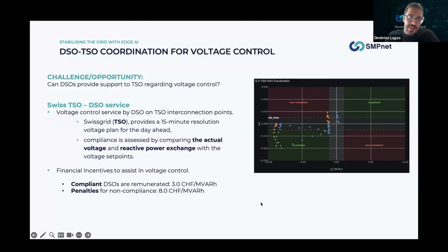And through this service, there are financial incentives for the system operator to be in the compliant regions. So they are compensated for reactive power that is in the compliant region, and they have to pay penalties if they are in the non-compliant region. And in that way, they can support the transmission system. Of course, this requires an advanced control at the distribution level to ensure that, based on the grid measurements they have at the point of connection to transmission, they are able to control their resources in a coordinated manner to ensure that they provide service to the transmission system.